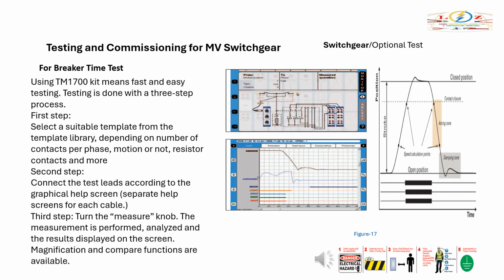For the breaker timing test, using the TM1700 kit means fast and easy testing. Testing is done with a 3-step process. First step, select a suitable template from the template library, depending on the number of contacts per phase, motion or not, resistor contacts, and more. Second step, connect the test leads according to the graphical help screen, with separate help screens for each cable. Third step, turn the measure knob. The measurement is performed, analyzed, and the results displayed on the screen. Magnification and compare functions are available.